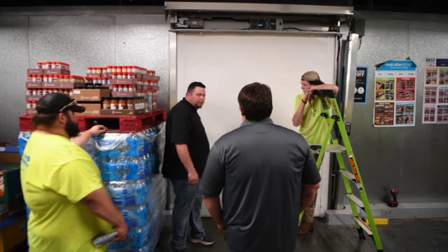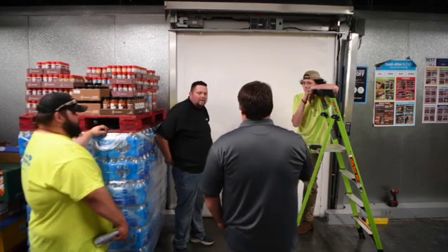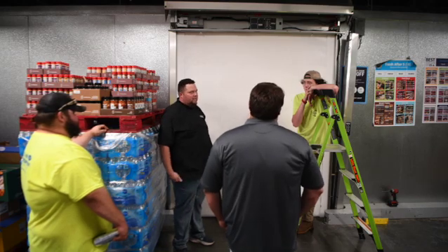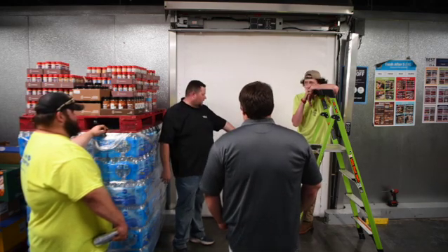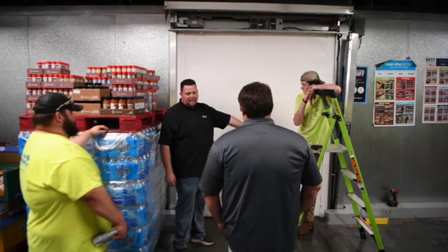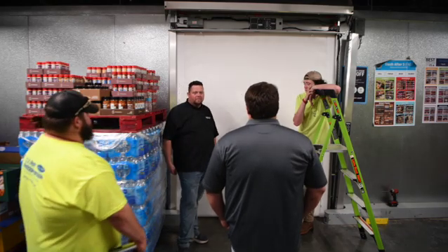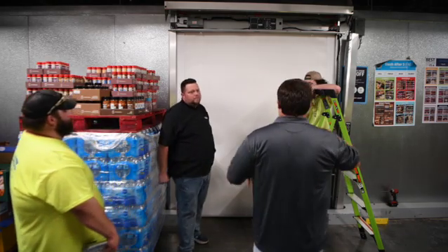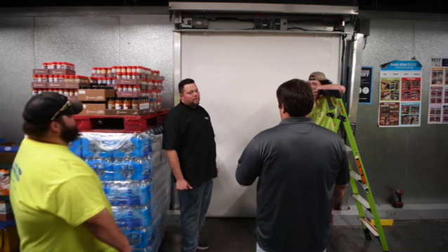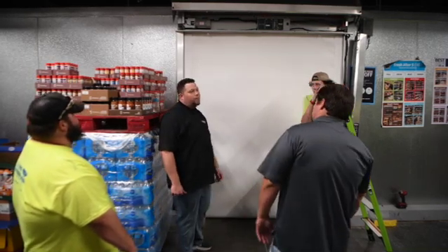You get those codes, you can call us. I fixed it, but that's what I did. I had one where I fixed the curtain and all. It tried to open and it was hung up on the side, probably wrinkled here, hung up there with the tension pipes against the side, and it just stalled the door out, and it gives you that EOF one. And that's what we were talking about, because I didn't know if somebody going through the recording was hitting it, messed it up or something, but I'm thinking now it's the adhesive that's catching it on that side. Yeah, very well could be.